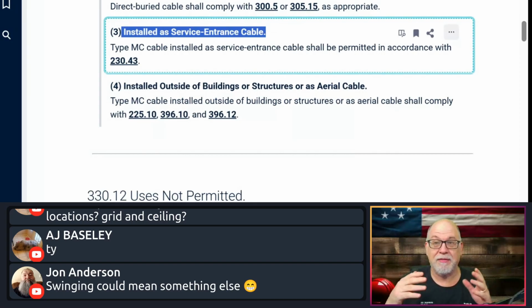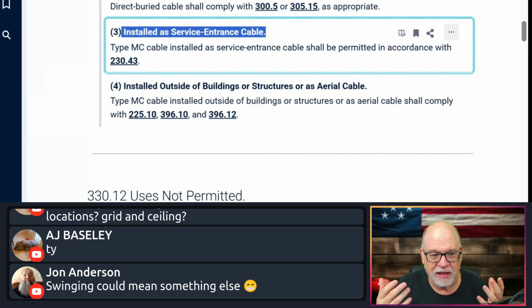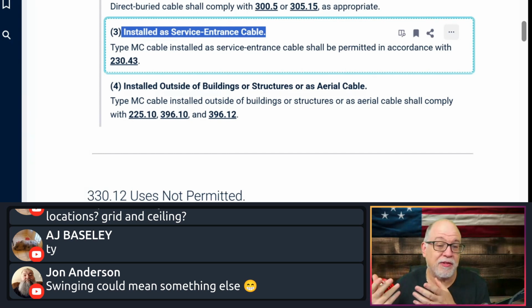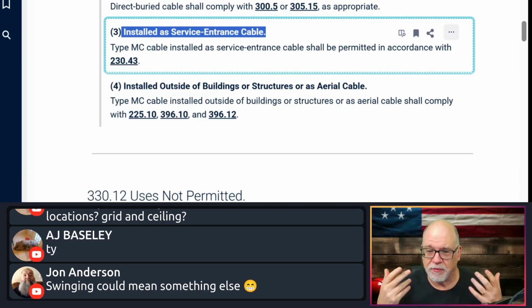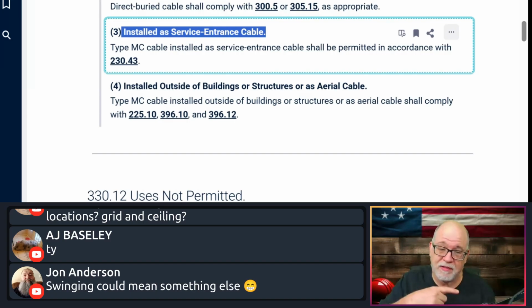So even though your SE cable looks like just a glorified non-metallic sheath cable product, it's still not for a location subject to physical damage. You can't put it there, but neither can you do MC. But again, that's all determining whether it's subject to physical damage or not. And you got to make that ruling, or the AHJ's got to make that ruling. Okay. But you can use MC for service. And I would say PVC jacketed MC, probably more problematic. But again, it might be easier than doing some type of raceway, like EMT or rigid or any of that type of thing. Obviously, it'll be a little easier.